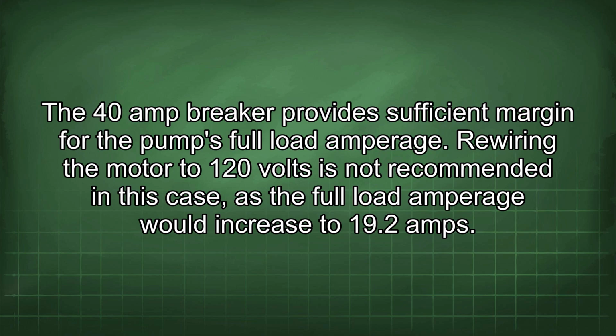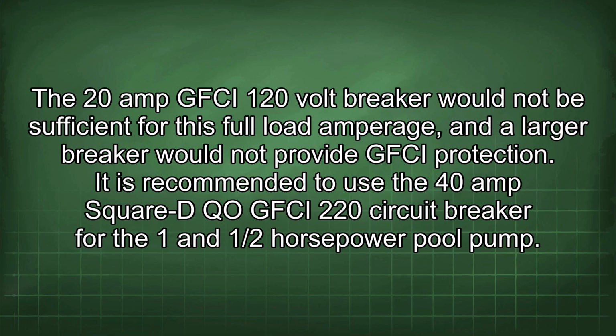Rewiring the motor to 120 volts is not recommended in this case, as the full load amperage would increase to 19.2 amps. The 20 amp GFCI 120 volt breaker would not be sufficient for this full load amperage, and a larger breaker would not provide GFCI protection.